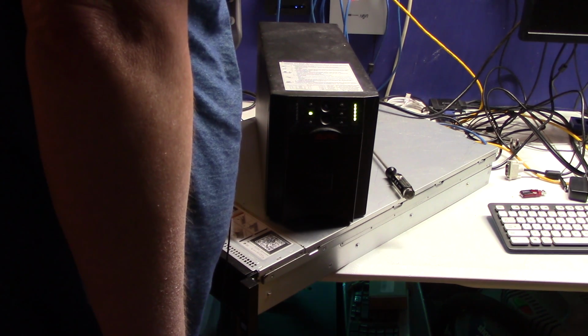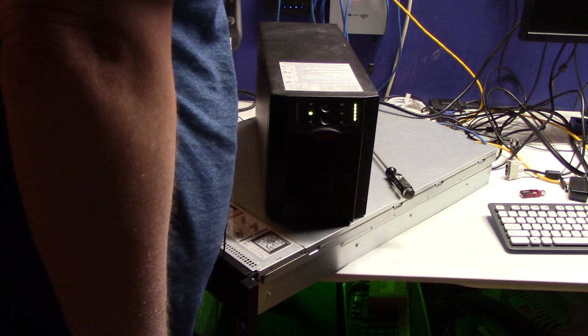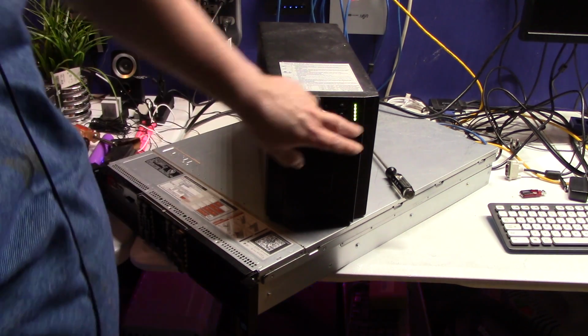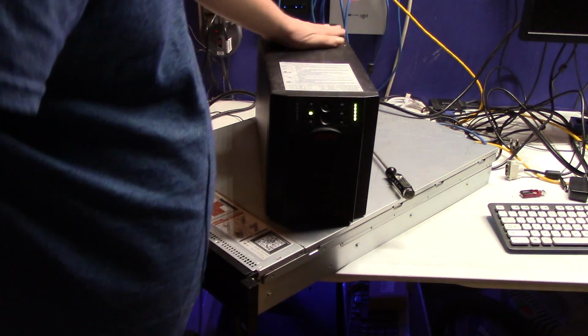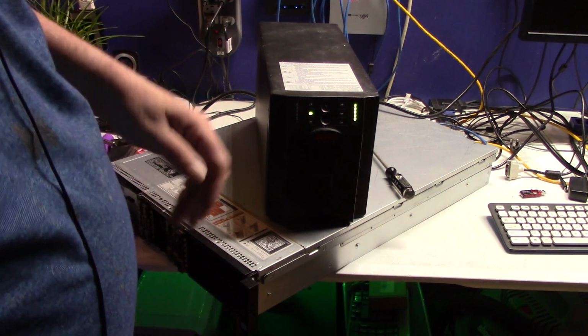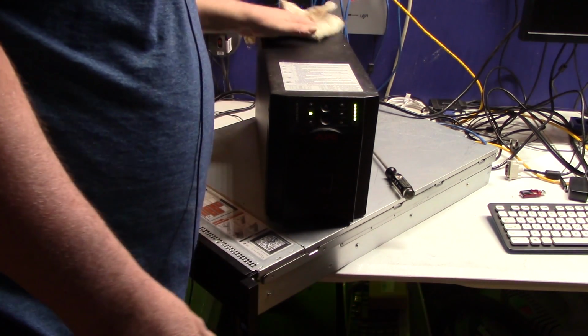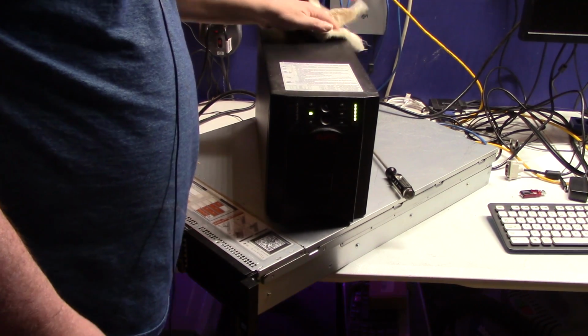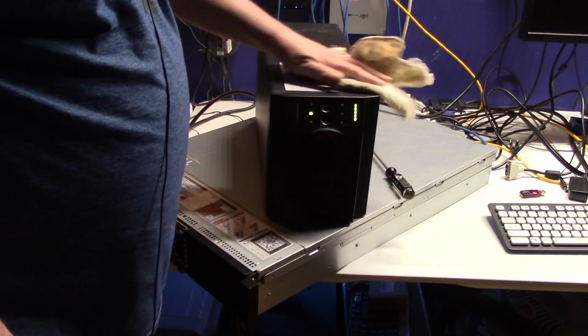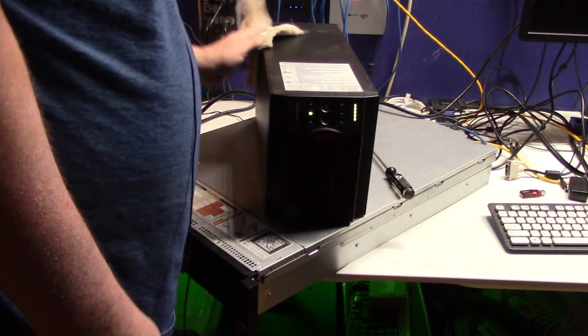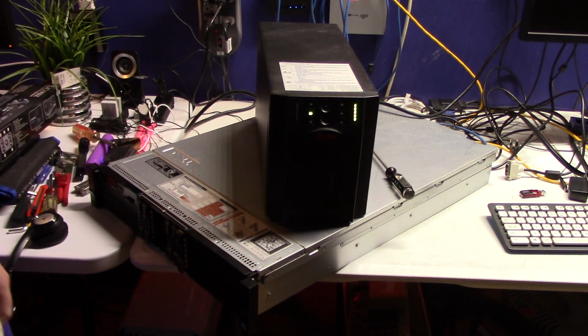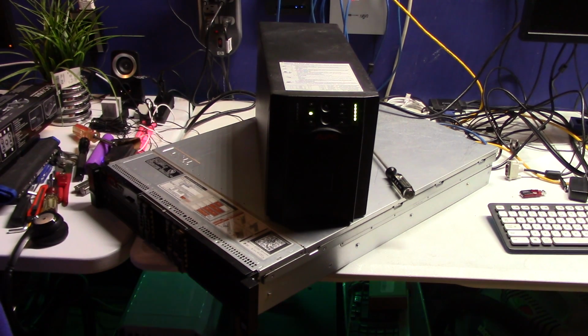You'll notice that once I put this back into the rack, the battery light starts flashing. That was the whole reason I replaced the battery, but I misinterpreted that. I have a network card in this UPS, and if I had checked it, it would have told me what the issue was, but unfortunately I did not check it.